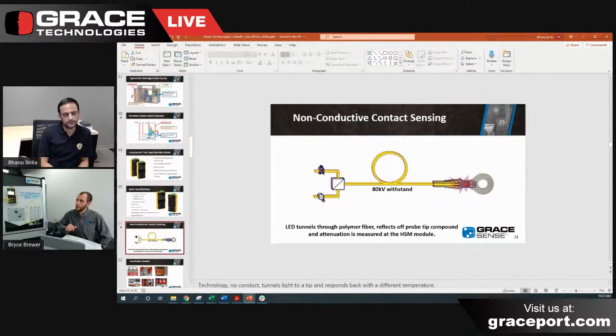Absolutely. So from the head unit here, it is a fiber optic out to the connection point. It sends an LED pulse from here, and it goes out to the tip that is right there on your ring lug on the equipment. That has a phosphor material in it that will change its reflective properties based on temperature. Then it's reflected back to the head unit where it's read, and that's where it's able to determine what temperature it is, all non-conductively from the low voltage compartment.